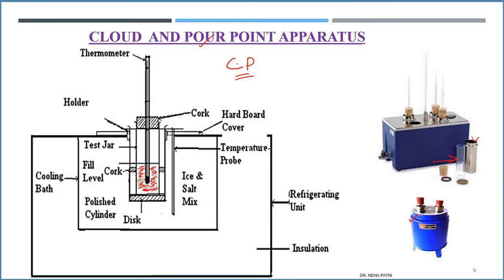Now you have to wait for the pour point. Pour point says that when it stops pouring. So what you can do is, once it's almost set, you can tilt the tube and see if it is still flowing. If some of the drops are still flowing, then you put it back inside the container and again cross-check. Then if you find that the boundary has stopped pouring, it ceases to flow, that temperature is your pour point.